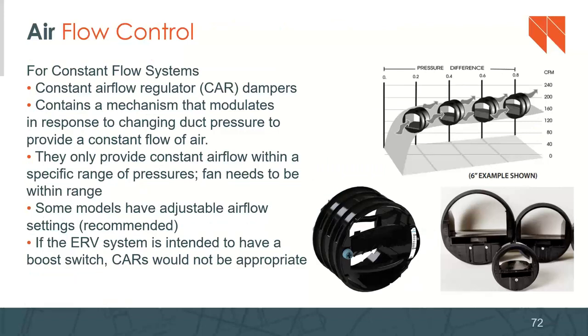Wanted to talk about flow rate control. There are these kinds of dampers called CAR dampers, constant airflow regulator dampers. They work great on constant airflow systems because it uses a blade technology that can sometimes be set at the factory at the specified flow rate. So let's say you want to achieve 20 CFM of exhaust air out of a bathroom, you can buy a CAR damper that is set to 20 CFM. As long as you achieve the static pressures that are required within the duct system, you're going to get very close to that 20 CFM.